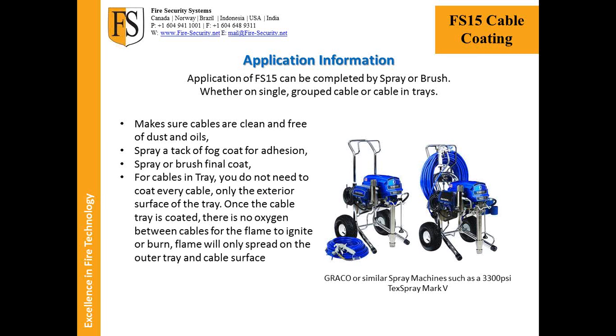Yep. So for application information, as we discussed, it can be completed by spray or brush, whether on single grouped cables or cables in trays. So the application or the preparation, which is all on our website, www.fire-security.net, in our download section, outlines all of our application requirements. But in a nutshell, we have to make sure that the cables are clean and free of dust and oils. And that could be just vacuuming those cables, wiping those cables with a dry rag.